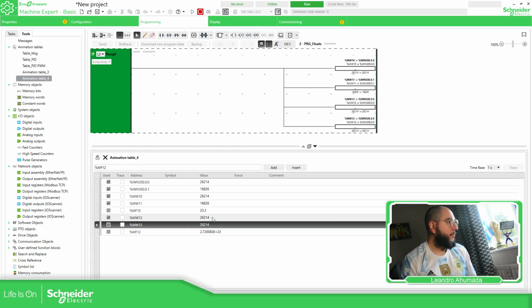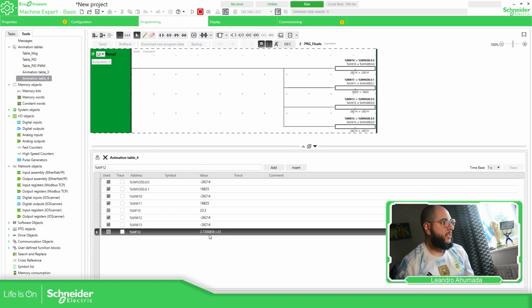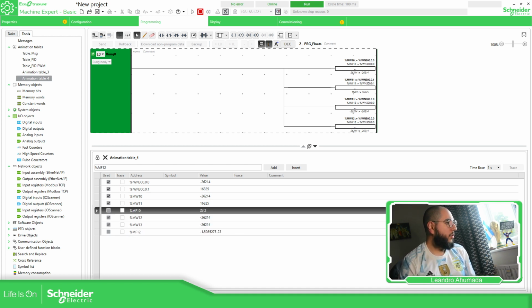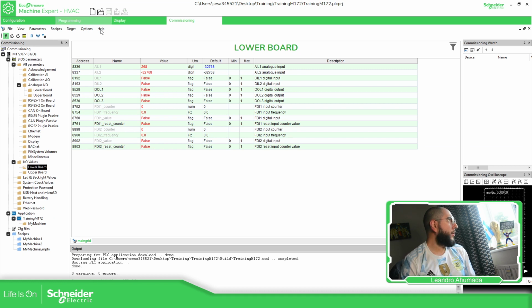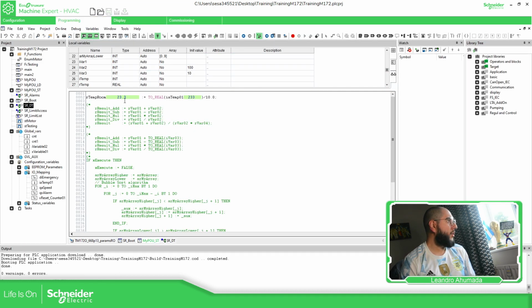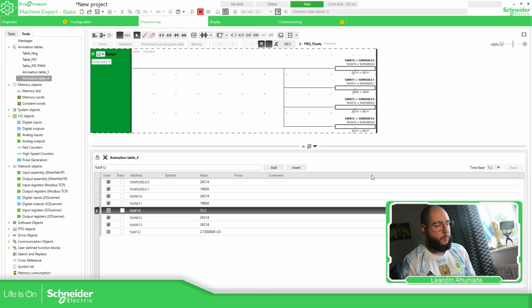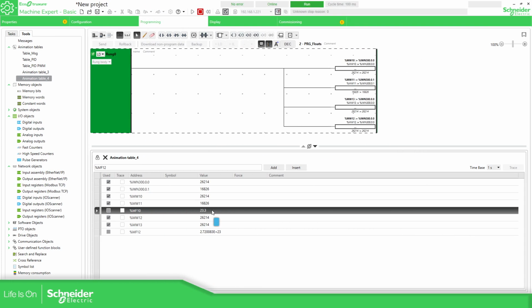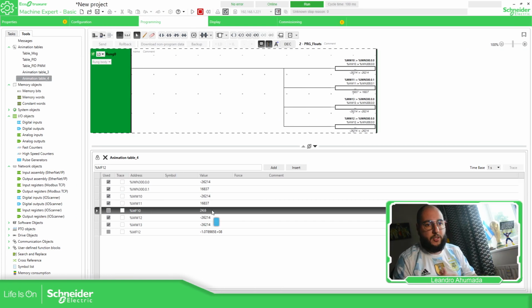And here you can see that I swapped them, and the number doesn't make sense. So let's check on the PLC on this one. 23.3, and then reading 23.3. Okay, let me just touch the sensor. It's not this one, the other one. Okay, there we go. As you can see in there, it's changing. It's an actual sensor, this one.